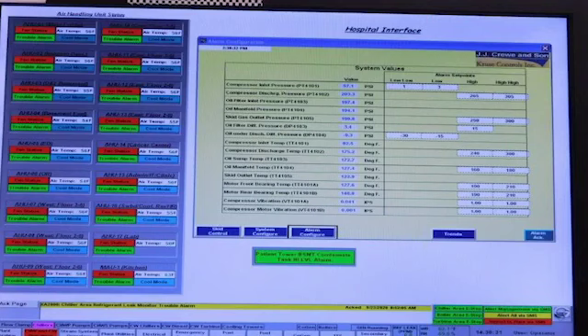We also have a hospital interface screen where we can see all the hospital's air handlers and pressure reducing valves. The steam system serves 4 primary PRV points in the hospital, and we send pressure at 150 PSI, and it's reduced down to 15 PSI for the most part inside the building. We also have the hospital automatic transfer switch system. They have a gaggle of automatic transfer switches. We can see the status of those systems in an emergency, and after an emergency, we can make sure that all the ATSs have recovered to their normal positions as our diesel generator looks to come back to standby position.